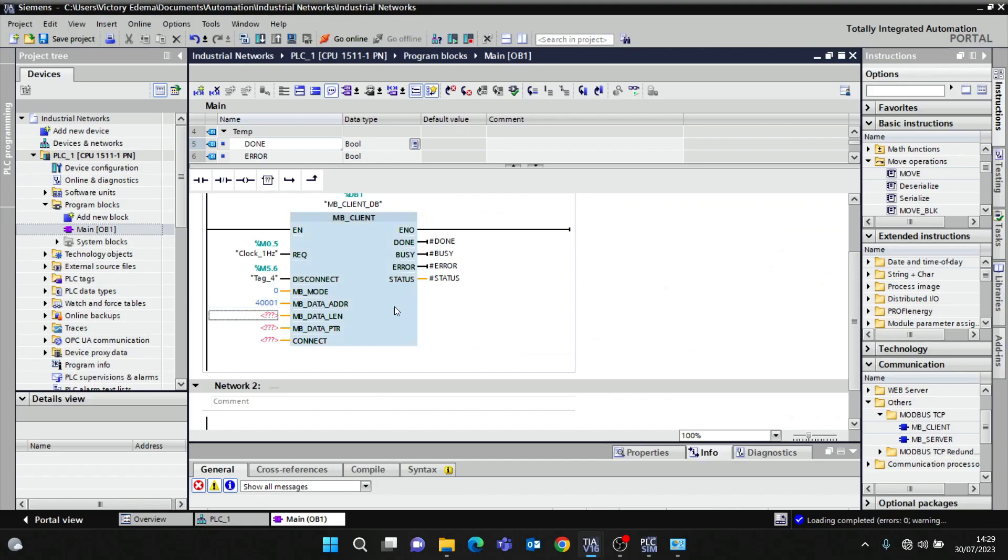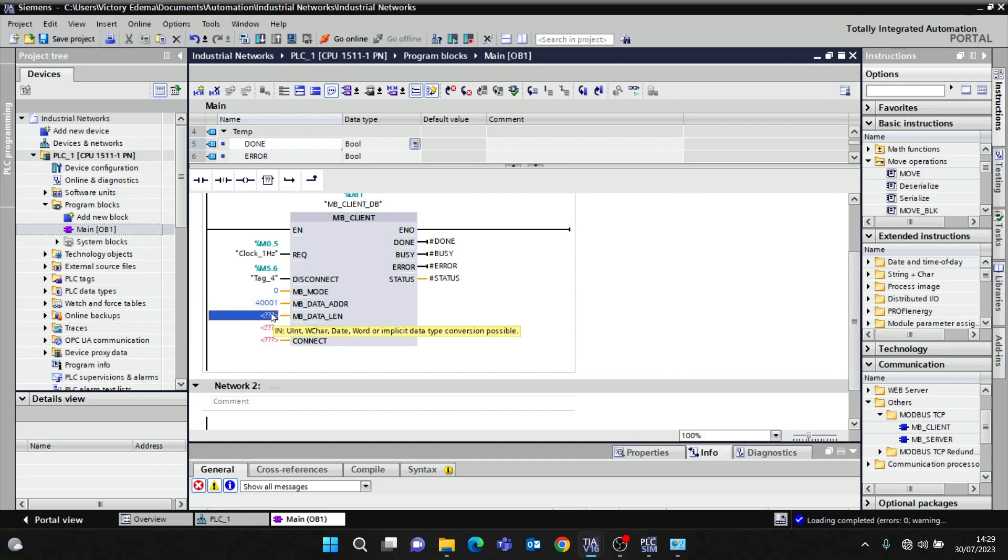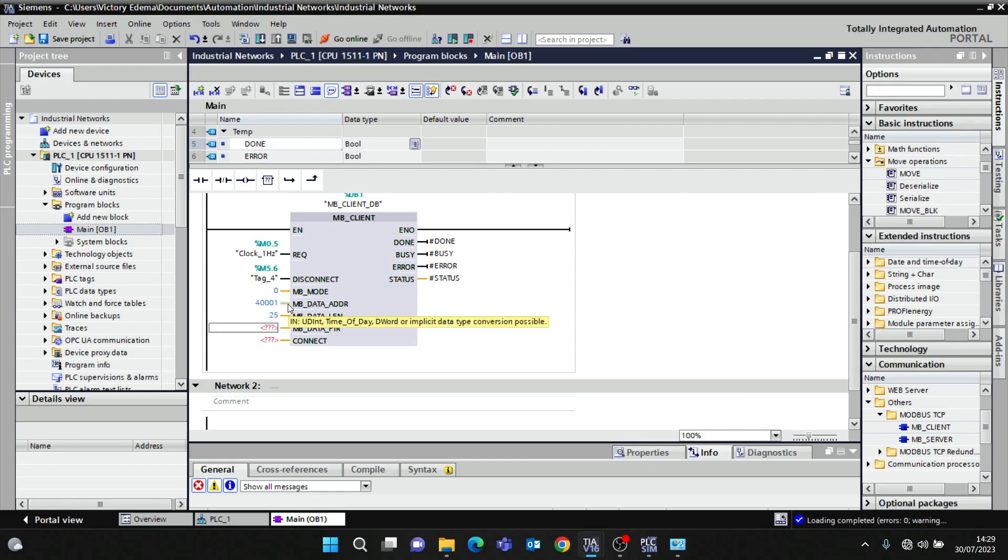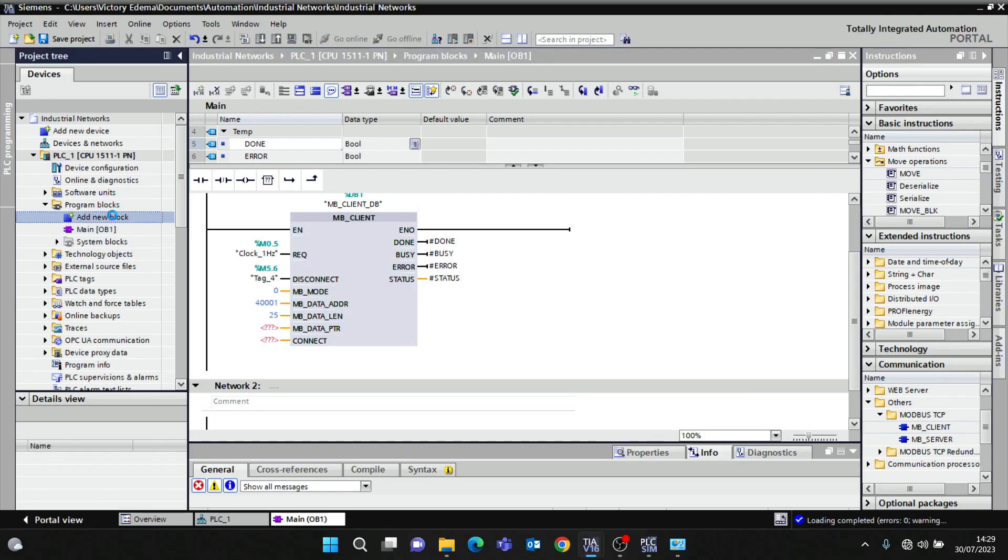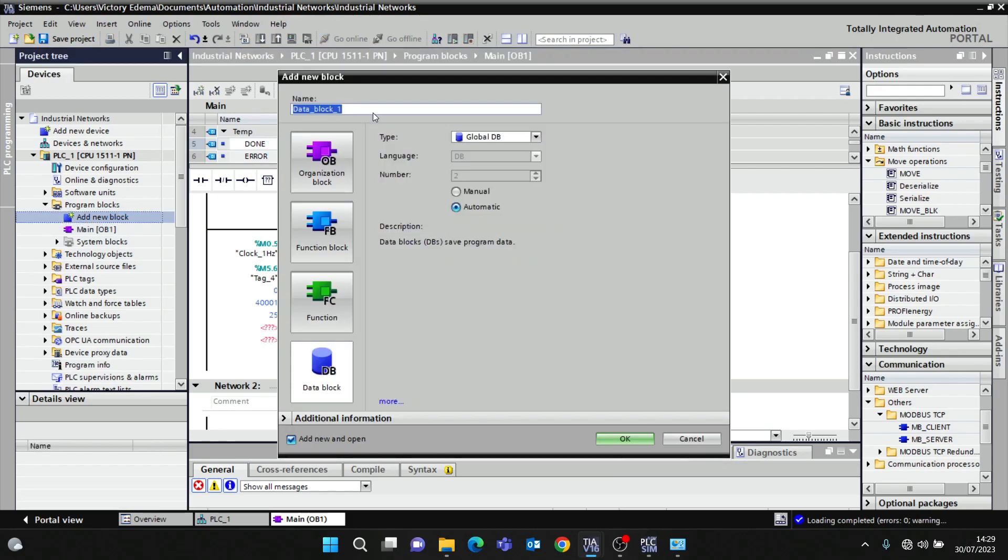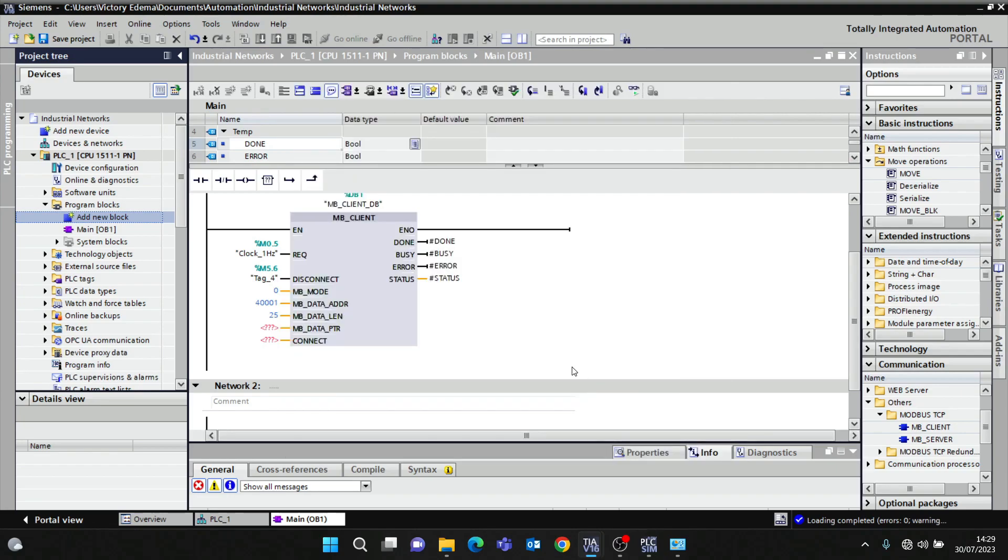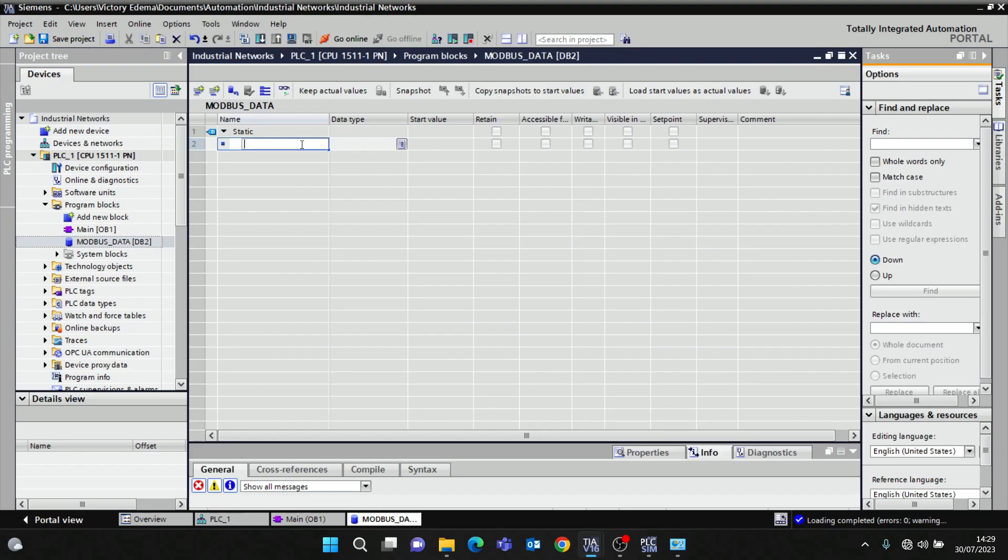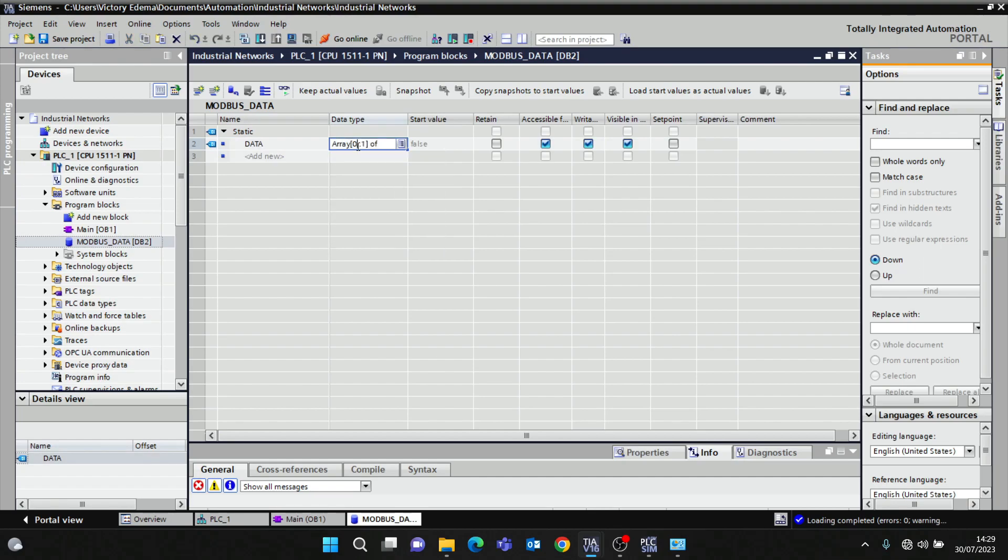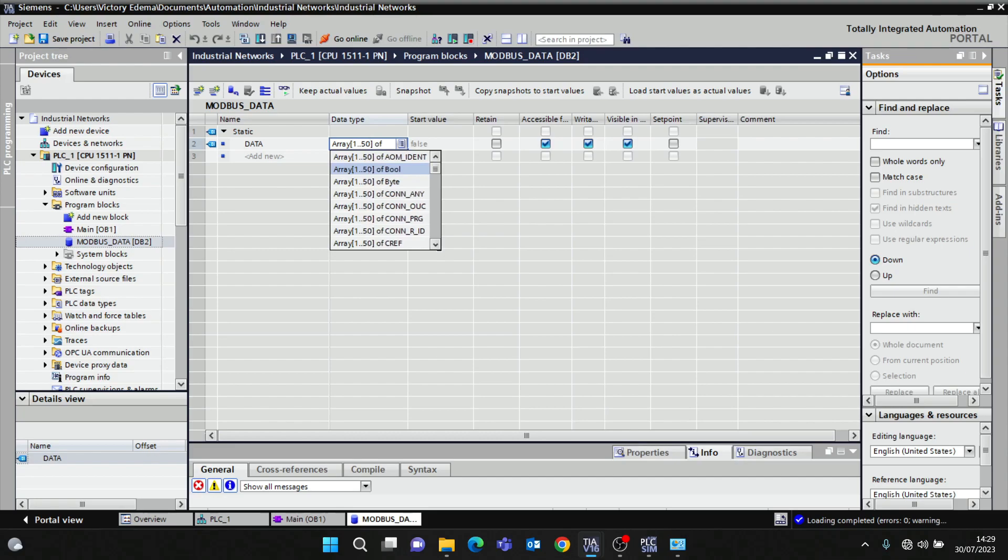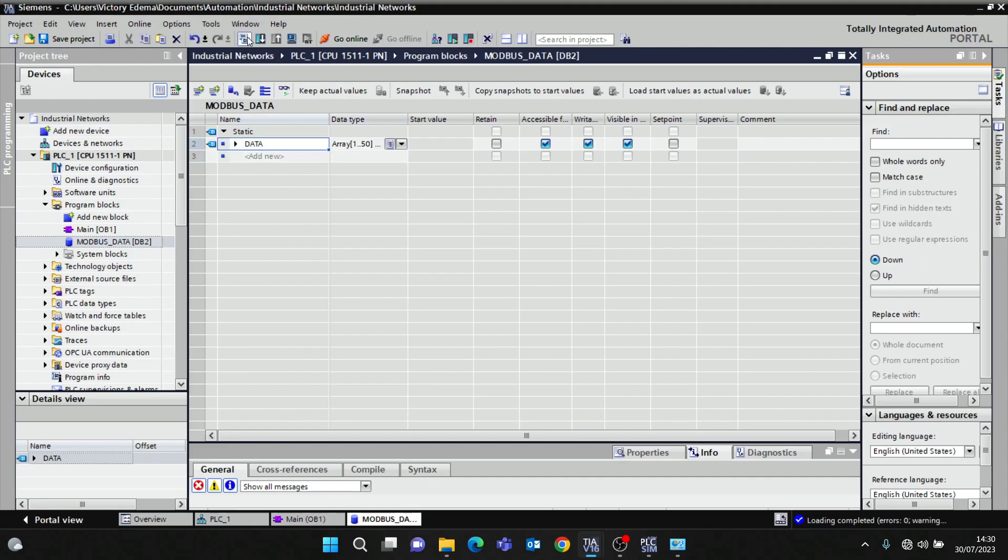MB_DATA_LEN - how many data do I want to read? For example, I want to read 25, so it means I'm reading from 40,001 to 40,026 in the data address. MB_DATA_PTR - this means where these data are going to be stored. I want to create a data block, call it Modbus_data, and call it data_array of 1 to 50 of integer.